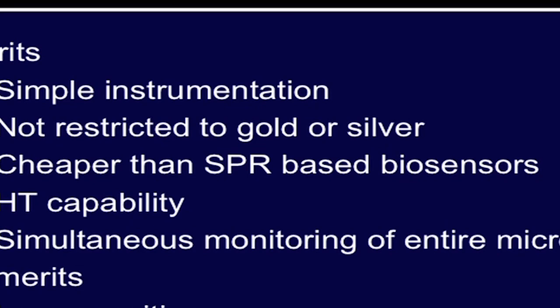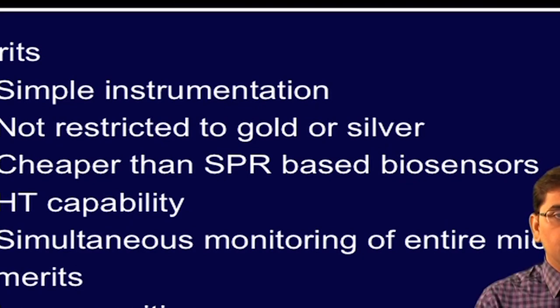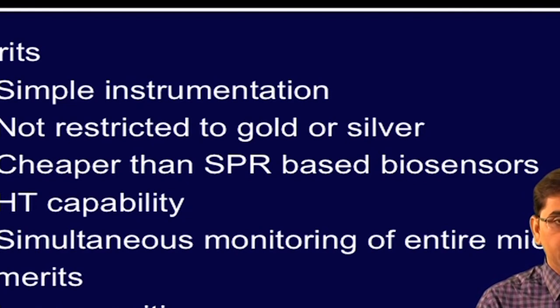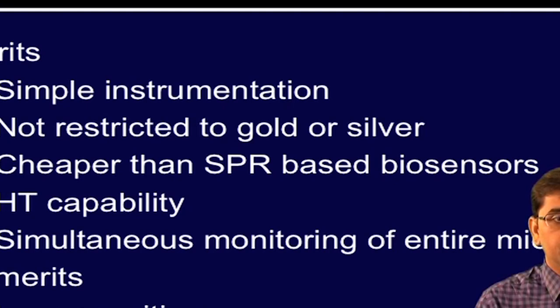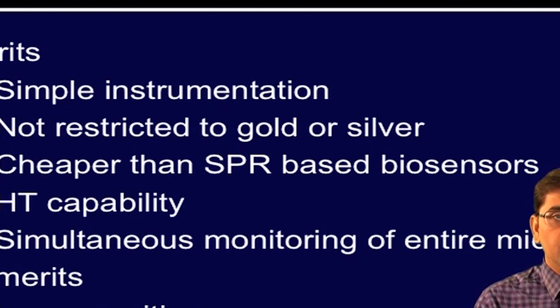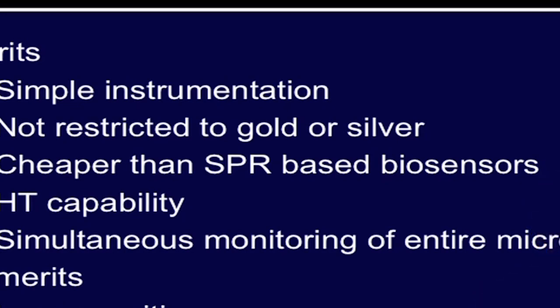Ellipsometry-based approaches have many merits. The instrumentation is very simple, which is unlike SPR-based instrumentation. It is not restricted to gold or silver surfaces. It is more economical than the previously discussed SPR-based techniques. It provides high throughput capability with simultaneous measurement of an entire microarray. The demerit of the approach is its sensitivity — it is less sensitive than SPR or SPR imaging-based techniques.